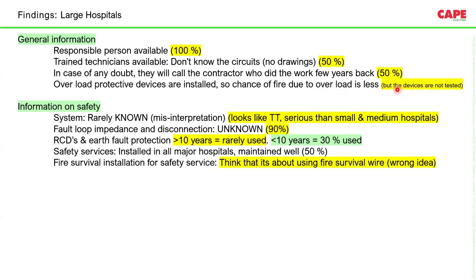You must have seen in our first-day video where there was a fire in an appliance. The ignition became a major fire because the protective device didn't trip. We generally call it fire due to overload or short circuit. Actually, the problem is that the fire is because of non-disconnection or delayed disconnection of the protective device.